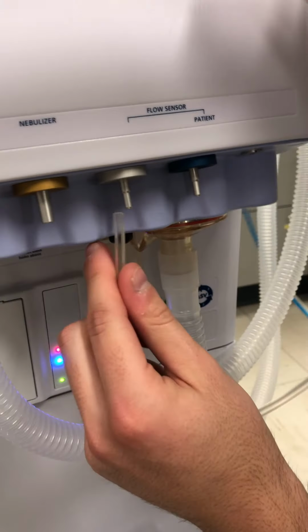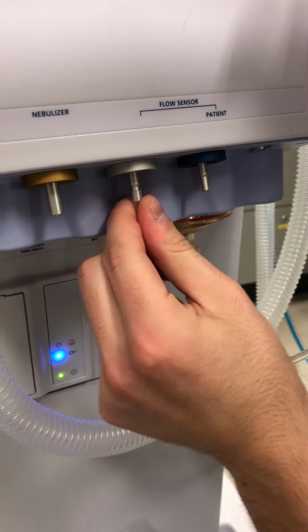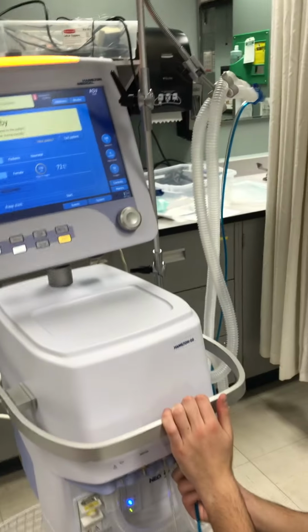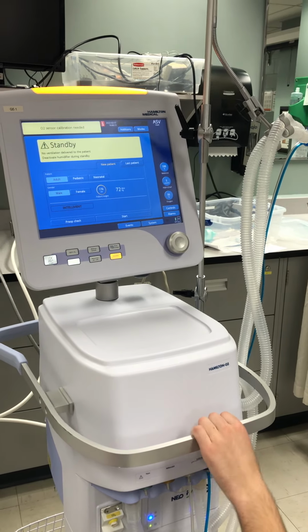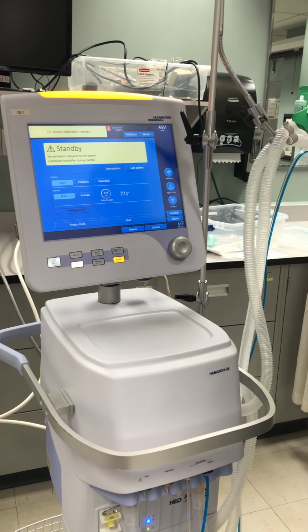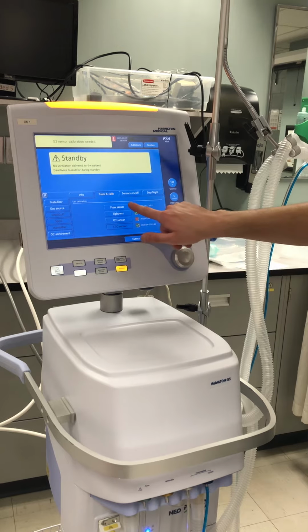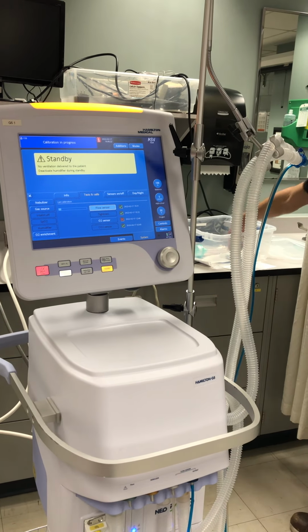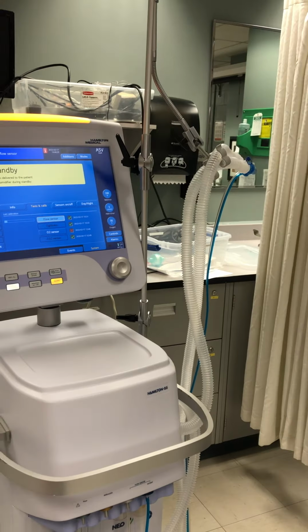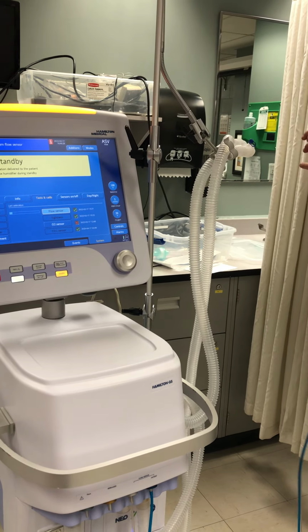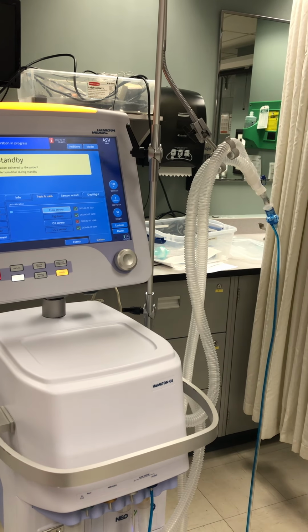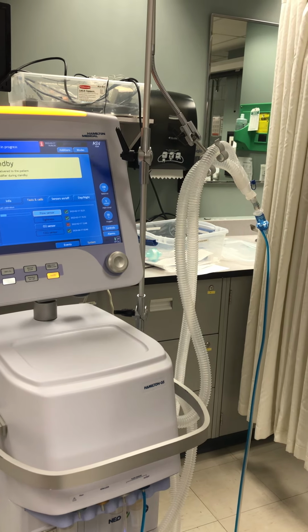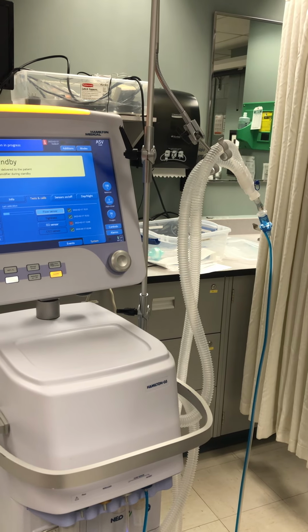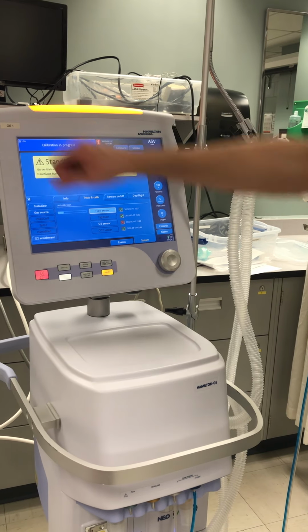Blue, white. Blue, white. So just color code it. Stick it on. And why are we running all of a sudden? Either way, to calibrate the system, pre-op check, you press that. Flow sensor, you press that. You will also need this adapter for later. So it says turn flow sensor, so you want to take it off, put on your adapter, turn it around, and put it on. Calibration occurring. And with the calibration, you just want to read over here while it does its thing.